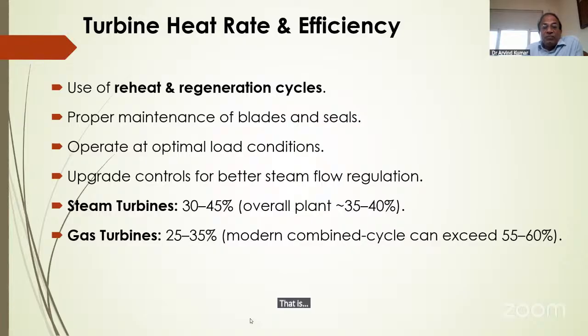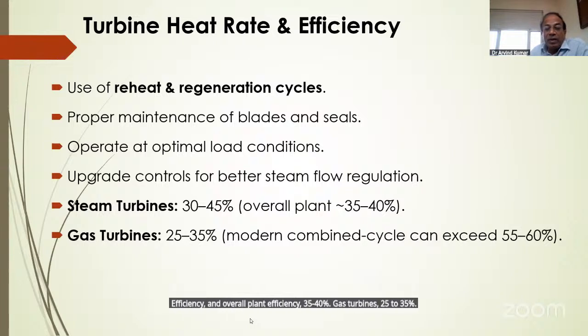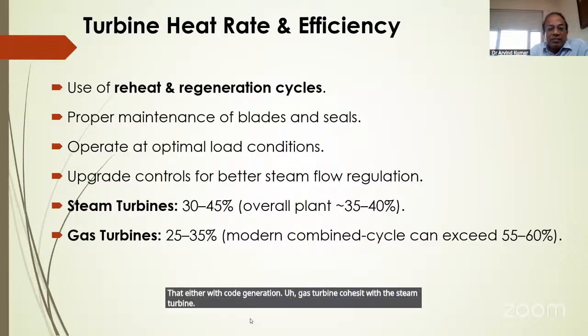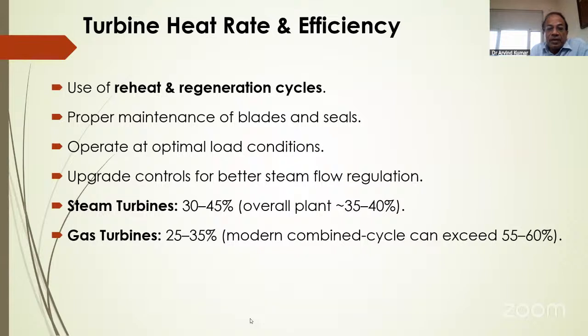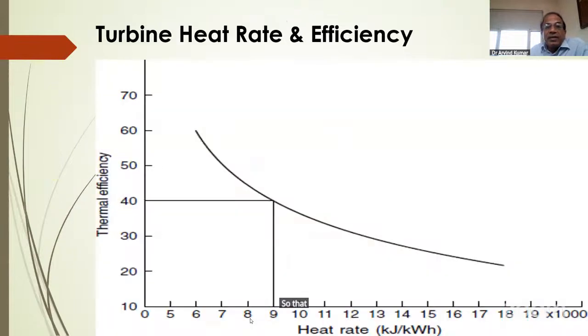Steam turbine efficiency is 30 to 45%, and overall plant efficiency is 35 to 40%. Gas turbines are 25 to 35% in open cycle, and in combined cycle coupled with the steam turbine, up to 55 to 60% in combined heat and power generation, that is with cogeneration, where a gas turbine is cogenerated with the steam turbine. So that is the turbine heat rate and efficiency.